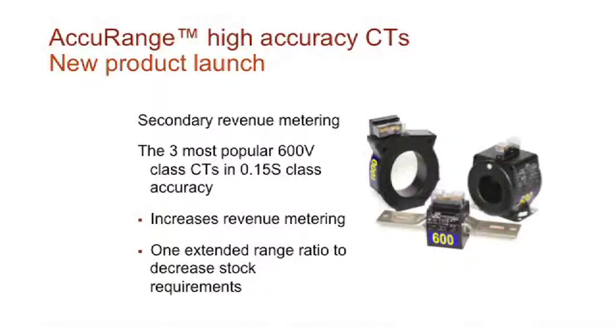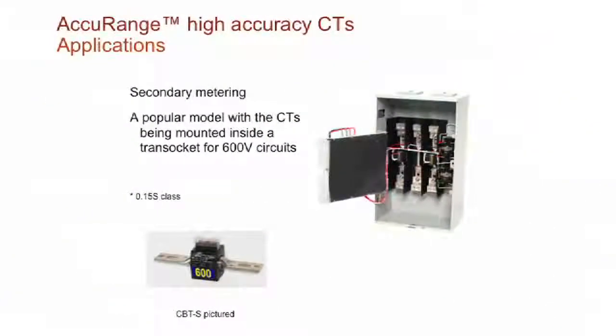These are the vast majority of current transformers that a utility would use at the secondary revenue metering. Again, this will increase revenue metering, and one of the other benefits to these also is that you can decrease the amount of stock that you have, because these 3 CTs right here, these specific ratios, will pretty much be anything that a utility would use in the course of any kind of secondary revenue metering.